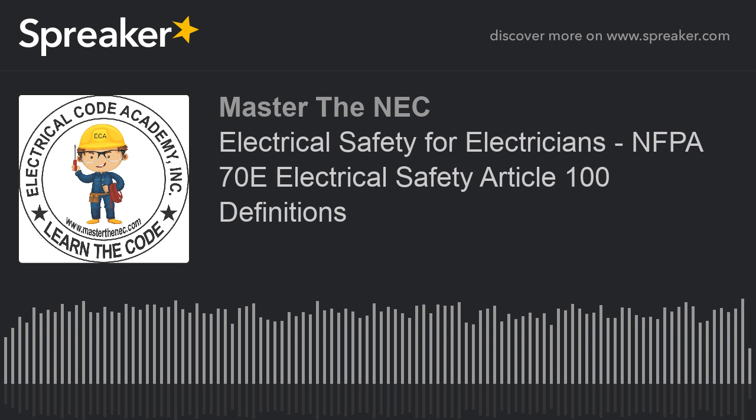And we want to just be careful with that. The next one we'll look at is the limited approach boundary. So what is this? It is the approach limit at a distance from the exposed energized electrical conductors or circuit part within which a shock hazard exists. So you have the conductors that are energized. Obviously, they're energized in the equipment, they might go to a terminal, then you have a lot of bus bars or parts. All of this, there is an approach limit or a distance that you can get to that we call the limited approach boundary, that point where you can't go past.